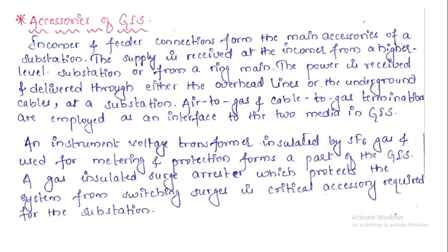The supply is received at the incomer from a higher level substation or from a ring main. The power is received and delivered through either overhead lines or underground cables at a substation. Air to gas and cable to gas terminations are employed as an interface between the two media in the GIS.